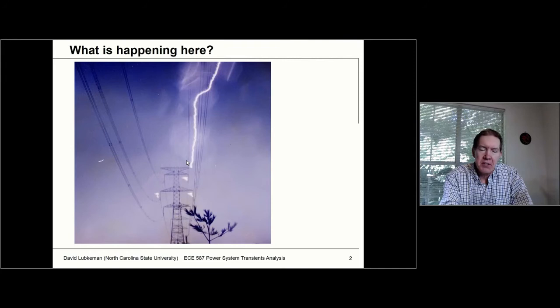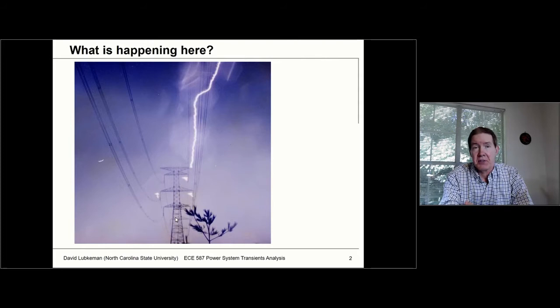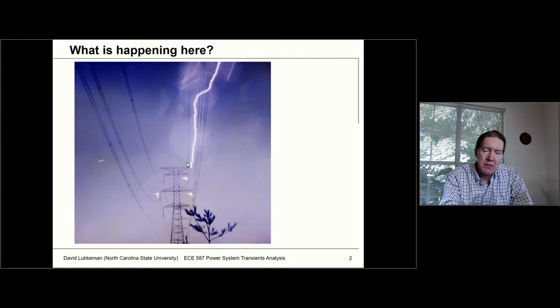What's happening is you have ground wires attached to the towers, and the towers are grounded. When the lightning strike hits, the lightning is trying to find a path to ground. Some of the energy goes one way down the ground wire, some goes the other way, but a lot of this energy travels down the tower — and this tower basically looks like a transmission line, like a cable. When this lightning traveling wave goes down to the bottom of the tower and comes back due to reflection, we see an increase in voltage.